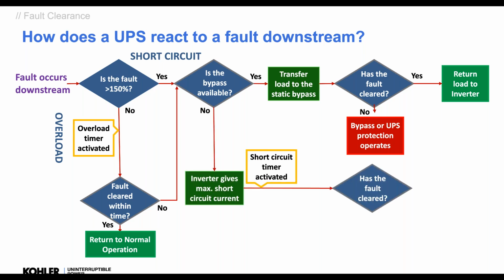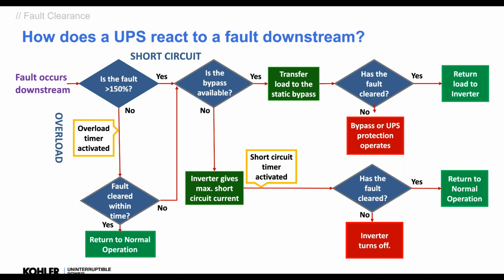Okay, if the bypass is not available, we're in a mains fail situation. The inverter will go into short circuit current limits. Okay, so it will give the maximum current it can, typically with hardly any volts, it's just pumping current at low voltage for a very short period of time. Try and use that to clear the faults. Okay, if it clears the fault, it comes out of current limit, goes back to normal, leaves an alarm. Okay, if not though, the inverter will turn off in some form or fashion at some point, and that depends on the model, the make, things like that. But typically it will turn off at some point, to protect itself as much as the load.